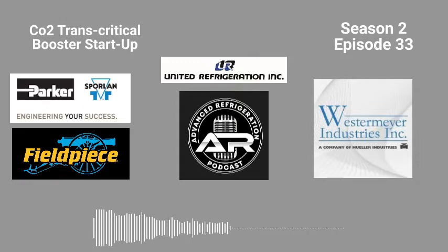I'm not really worried. Well, wait a minute. Because the medium temp or low temp compressors have different reliefs on them. Don't you have to separate that from the system, because the reliefs on the compressor are going to be at a way higher pressure on the suction side? You're muted. The transcritical, you're only doing the transcritical side, the TC side. So it would be the medium temp compressor discharge on all the way down to the drop leg. So you're going to blow it.